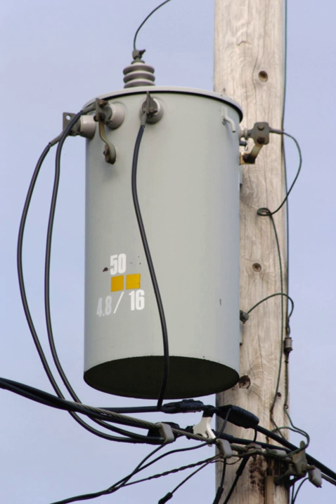From the transformer, power goes to the busbar that can split the distribution power off in multiple directions. The bus distributes power to distribution lines, which fan out to customers. Urban distribution is mainly underground, sometimes in common utility ducts. Rural distribution is mostly above ground with utility poles, and suburban distribution is a mix.